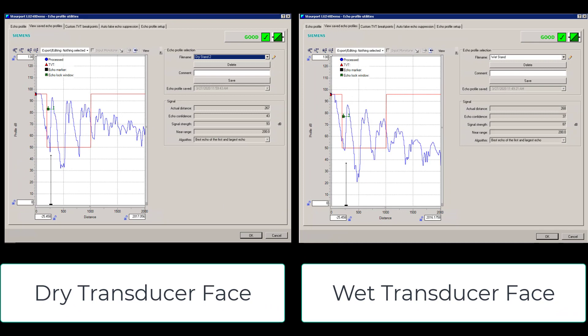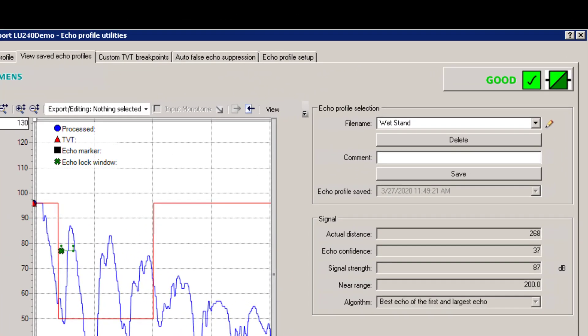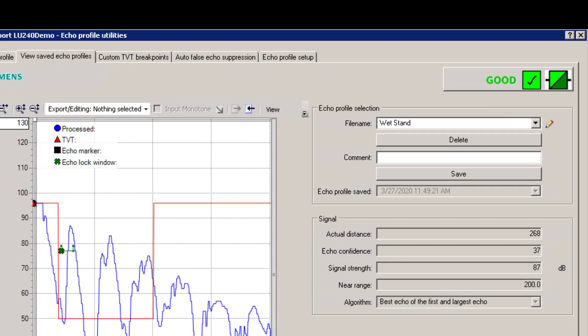If we then have a look at the transducer face when it's wet, we've got a slight change on the actual distance—1 millimeter, it's still well within spec. The signal strength has dropped to 87, but all in all good echo profile and the signal is fine.